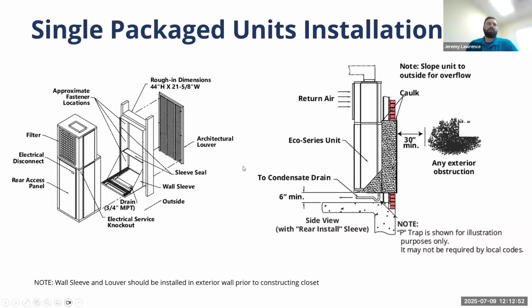As with the louver, because we need an exchange of air, any water, snow, or moisture of any kind that gets past the grill will hit the condenser coil, drain down, and then go back outside as well. So there's no way of water getting past these units. Like I said, we've been installing these units, the Eco Series specifically, for over 30 years in Ontario, and we just have never had any water issues from exterior. The entire condenser section, this bottom section, is open to air through the condenser, which keeps the compressor cool and quiet. All insulated cabinets. There is an additional insulation panel kit that can be added if we're concerned about cold weather or frost or anything like that.